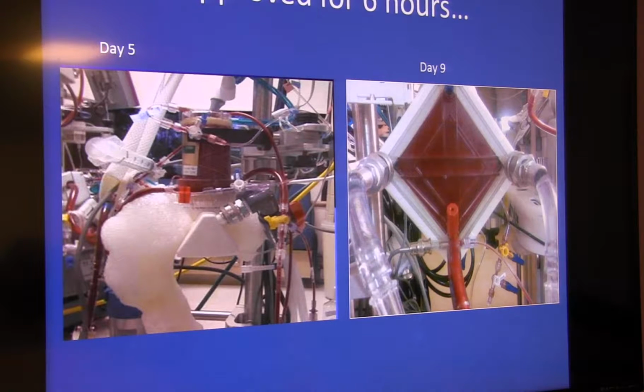So the way we have our protocols written is that there's protocols for titrating the patient's pH, and there are protocols to titrate the FiO2 to keep your post-oxygenator PaO2 greater than 250. I always forget whether it's 200 or 250. And the reason why I say that is because every 6 hours we get pre and post oxygenator gases off of the circuit. And when you're on rounds in the morning, you're going to have pre and post oxygenator gases. And one of the things that when you're in the beginning of learning, you initially completely disregard are those pre and post oxygenator gases, because you can't figure out what they're for. What they're for is to tell you about your oxygenator.